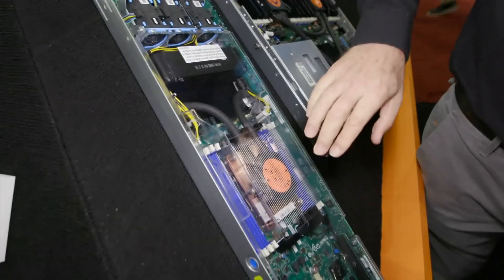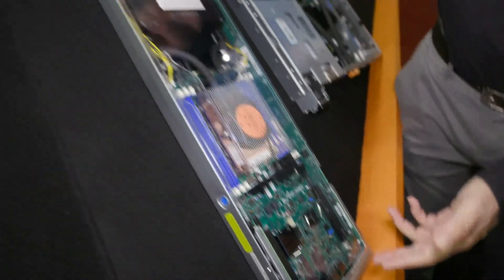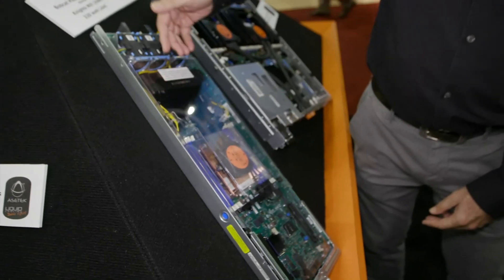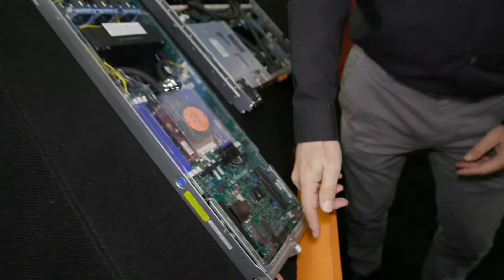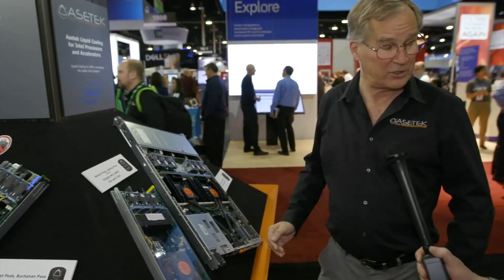What's exciting about this particular node is that it's different from our standard liquid coolers where we're taking the heat all the way out of the data center with liquid. Here what we're doing is enabling Intel's new KNM processors — 320-watt processors — to run in an air-cooled data center. This is a liquid-to-air heat exchanger. Air blows through that and cools the system, and the heat comes out the back in the air. That level of density isn't possible with a standard air heat sink.